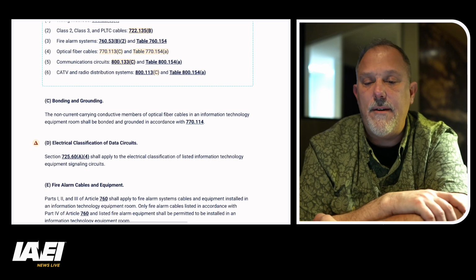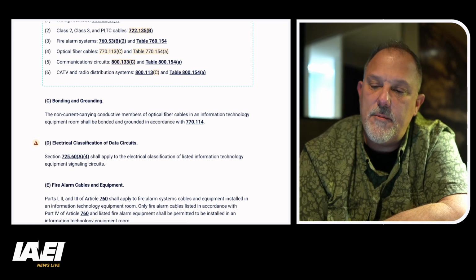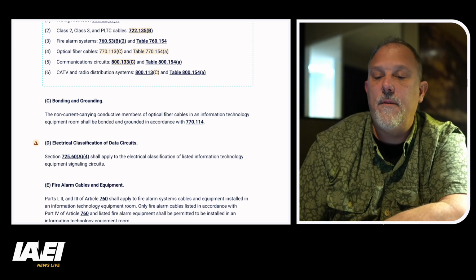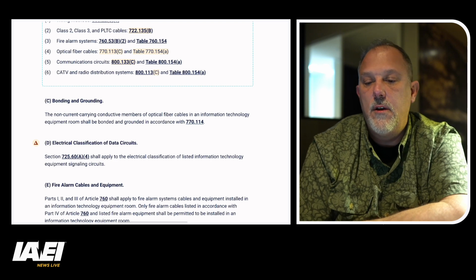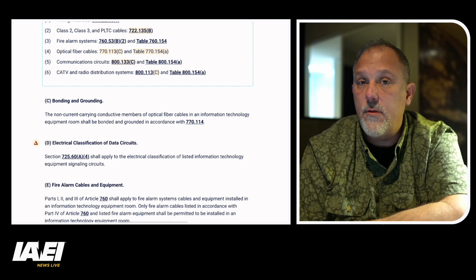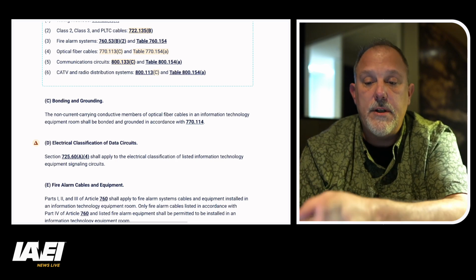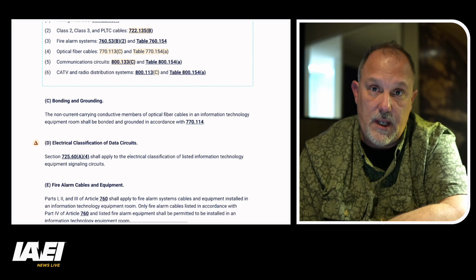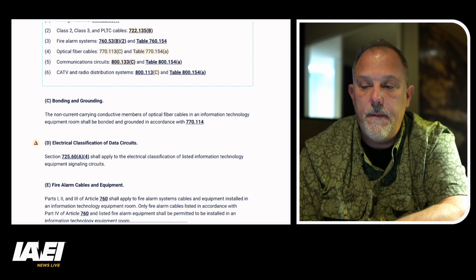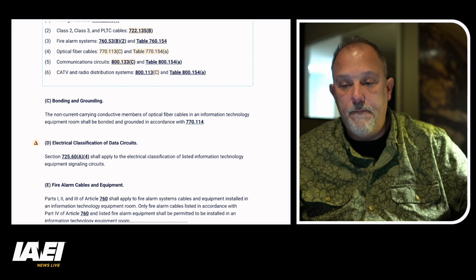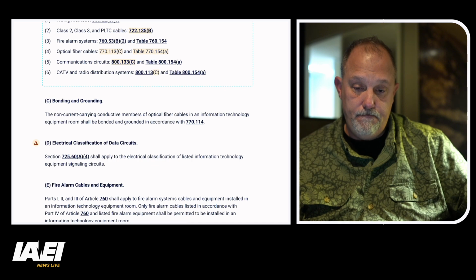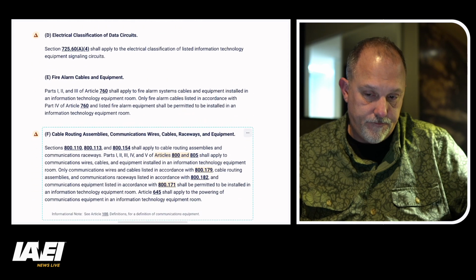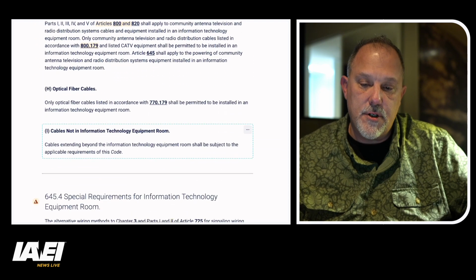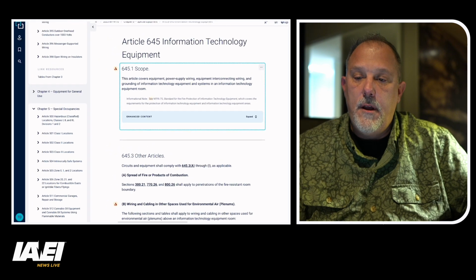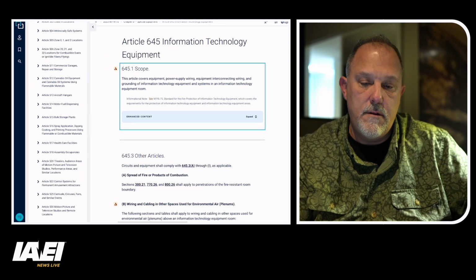And then you've got your bonding and grounding. And I'm interested, it says non-current carrying conductive members of optical fiber cables. So this is optical fiber cables, and it points you to 770, but I would argue Article 250 would apply to everything else. So just because that says bonding and grounding doesn't mean you can circumvent Article 250, because this language only pertains to optical fiber cables that are in an IT equipment room. You got your classifications, you have your fire alarm, cable routing, antenna, optical fiber cables. So there's a lot in this would be 645. Interesting.